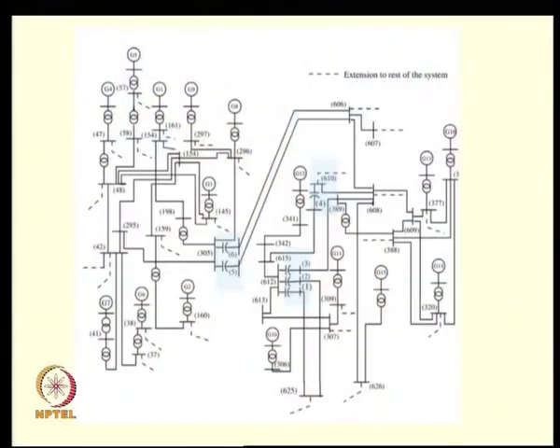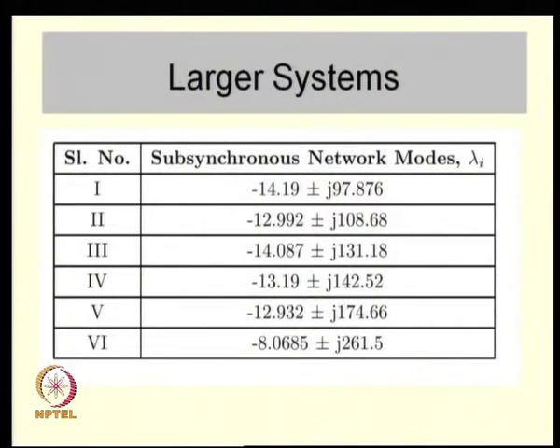For the particular system with six series-compensated lines, there are six sub-synchronous network modes, along with other network modes. This kind of analysis can be done with the tools discussed in this course — in principle, you should be able to formulate equations of this multi-machine system, each generator having several rotor masses, and do a linearized analysis. Remember it is a non-linear system, so you must linearize around an equilibrium point.